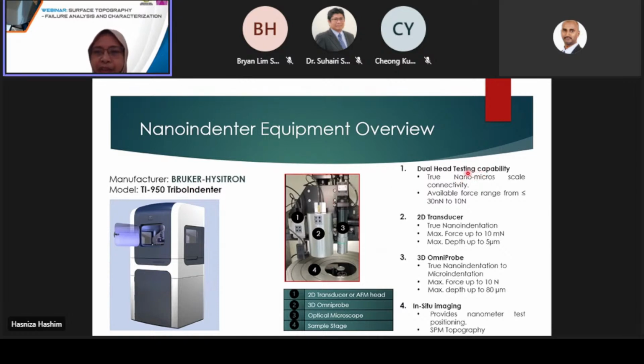The system comes with a dual testing capability, meaning that it provides an available force ranging from 30 nanonewtons up to 10 newtons. We have two types of transducer. We have what we call the 2D transducer, and we also have the 3D OmniProbe transducer. For the 2D transducer, we can apply a maximum force of up to 10 millinewtons and a maximum displacement of up to 5 microns. So it's really true nano indentation testing. For the OmniProbe, we can apply force up to 10 newtons and the displacement can be up to 80 microns. This is what we call nano indentation to micro indentation testing.